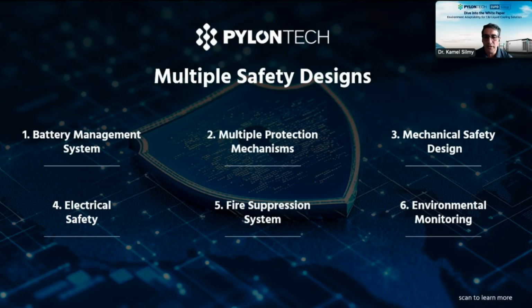We have 3-level short circuit protection: pack level fuse protection, cluster level protection, and system level protection. We also have 4-level software protection, featuring 3-tier fault alarm classification at levels 1, 2, and 3, plus an additional level 0 lockout function for enhanced system safety. This is in the BMS.